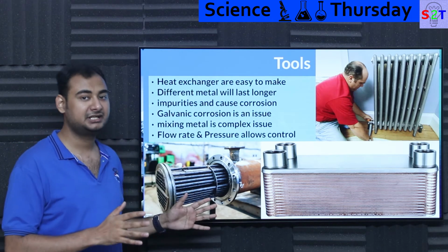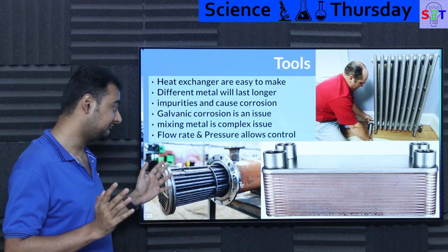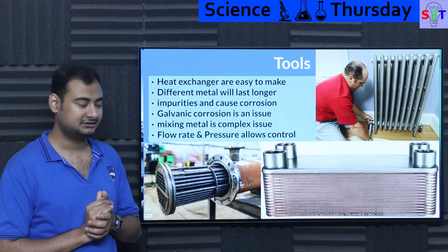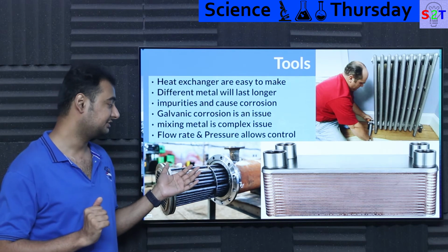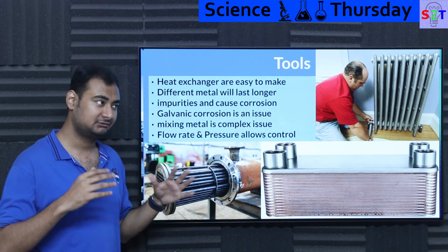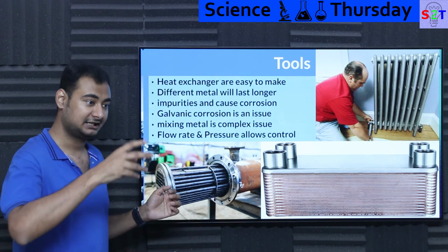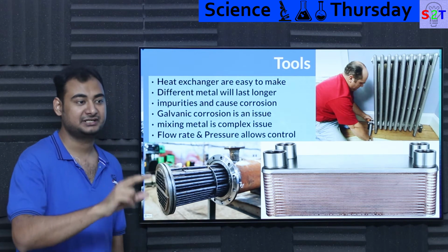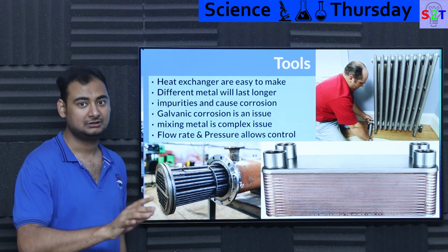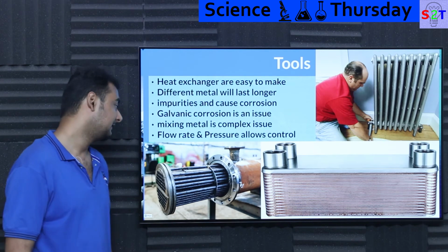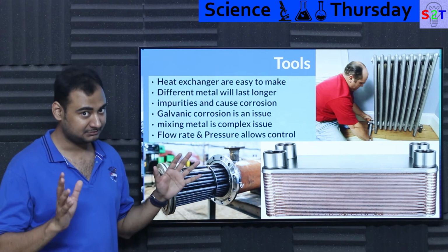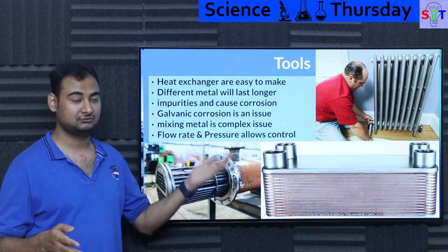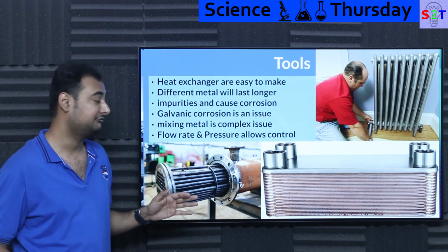There are ways of mitigating that issue. It has been done, especially for large heat sink operations, but you have to be mindful of that. Generally a sacrificial metal can be used, so you keep checking it: is it sacrificed? No, okay, I'm cool. Oh, it's sacrificed, okay, now replace it. So it has to be dealt with. It's a complex issue. If you want to mix, let's say, aluminum with copper, steel, iron and all that jazz, you have to be mindful of that.